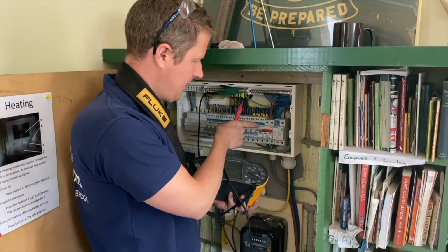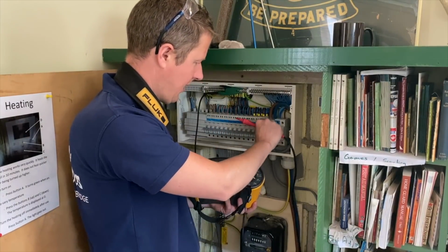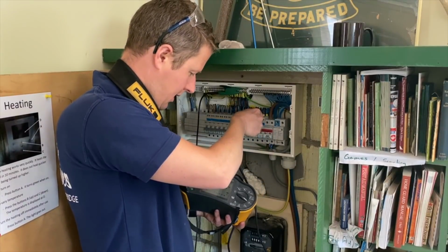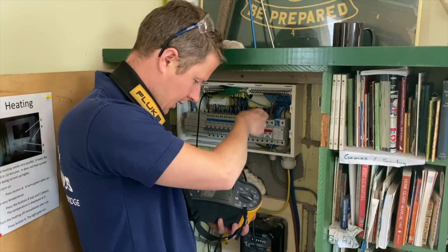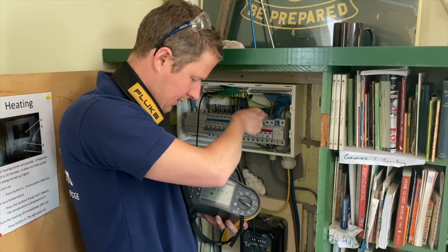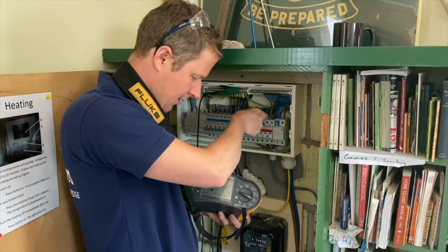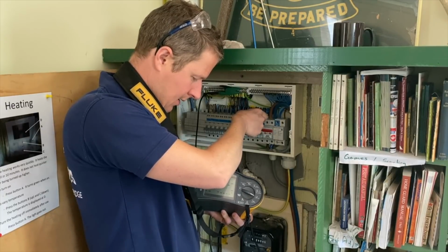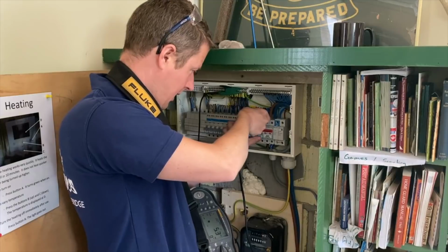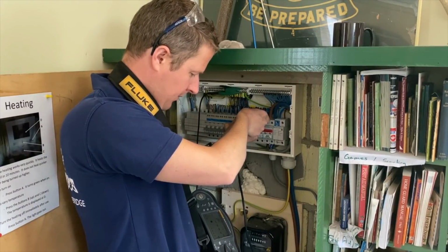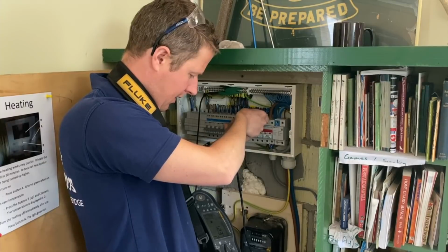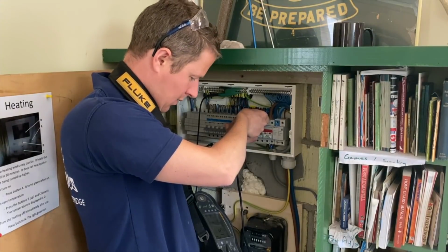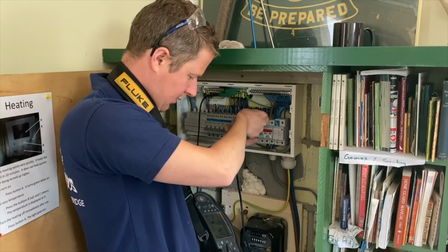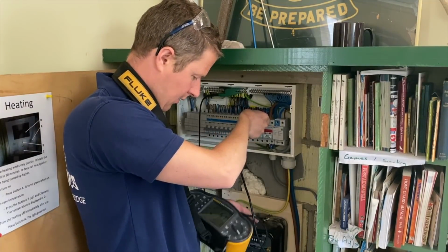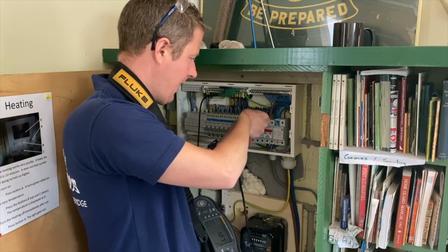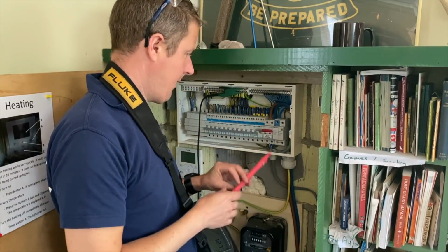The first test that we do is just a push button test, so press that and it should trip. That's good. Then we do the RCD test, and it measures half times at 0 degrees of the sine wave, then half times at 180 degrees of the sine wave, and it shouldn't trip. Then at 1 times it should trip, and it does 2 tests, 0 degrees and 180 degrees of the sine wave, and then we do 5 times the current rating, which is 150 milliamps, and that should trip again, and we do 0 degrees and 180 degrees of the sine wave once again. So that is our first set of tests done.